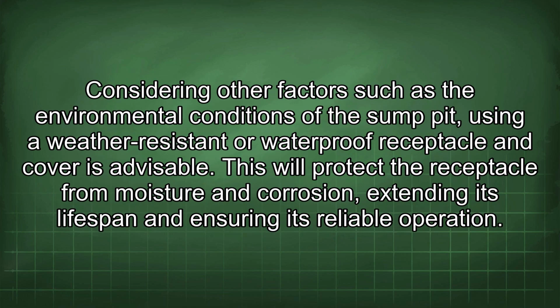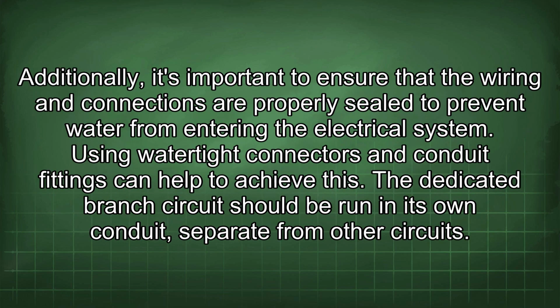elevator. Considering other factors such as the environmental conditions of the sump pit, using a weather-resistant or waterproof receptacle and cover is advisable. This will protect the receptacle from moisture and corrosion, extending its lifespan and ensuring its reliable operation. Additionally, it's important to ensure that the wiring and connections are properly sealed to prevent water from entering the electrical system. Using watertight connectors and conduit fittings can help to achieve this.